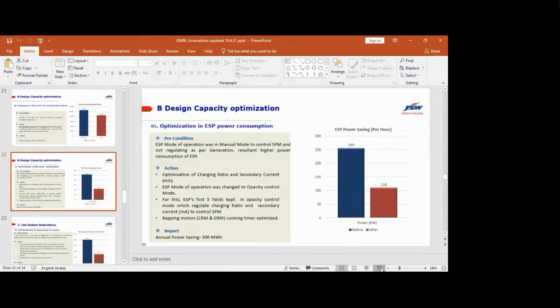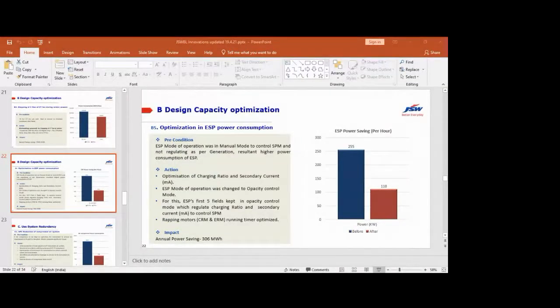Optimization in ESP power consumption. Earlier we operated the ESP in manual mode. In this, the charging ratio and the secondary current of the field remain constant. It was not regulating against the boiler load or generator load. So we put it into the EPOQ mode, the opacity control mode. In this, we did different trials to find at which charging ratio and secondary milliamps we get the best result for the SPM.